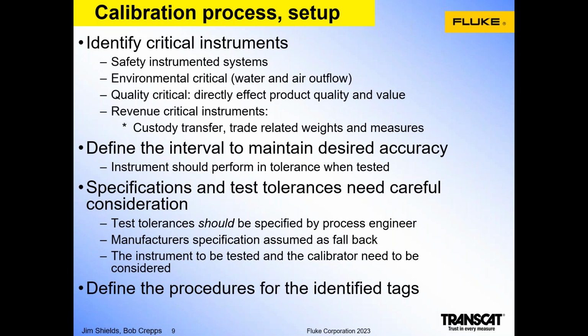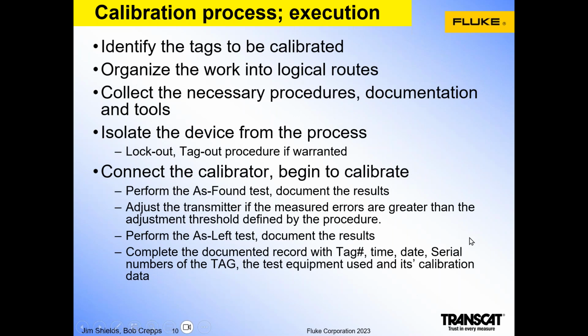But in the event that the device is critical and it's part of the quality control process, you must have some specification and document that defines what the specification needs to be, be it by the process engineer or from the manufacturer's data sheet. And the instrument to be tested and the calibrator to be used need to be considered. As I mentioned, the calibrator should be approximately 4 times more accurate than the device being tested. And then, of course, define the procedures for the identified critical tags that you've defined in your investigation into which tags to put into the database to be managed.